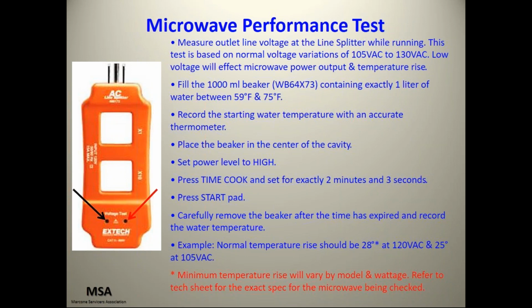That's 1,000 milliliters. The water should be between 59 and 75 degrees Fahrenheit. Again, you have to check it with your thermometer. You want to record the starting water temperature with an accurate thermometer. Place the beaker in the center of the cavity, set power level to high, and this is very important. Press time cook and set it for exactly 2 minutes and 3 seconds.